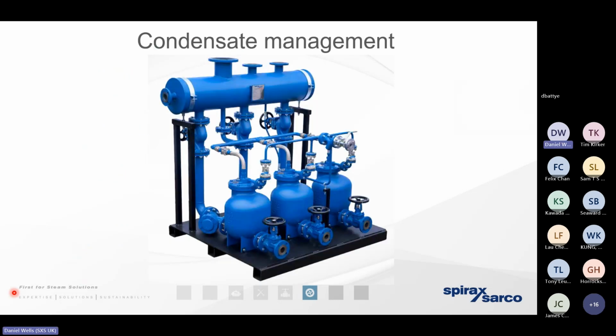Condensate management, as far as I'm concerned, is actually one of the most important and overlooked aspects of a steam loop. Yes, we mentioned heat exchange. That's the reason why so many of our steam using clients are going to have steam on their facility in the first place. We mentioned that steam trapping, in my opinion, is one of the most important components, because if we're not trapping the steam correctly and allowing the condensate to drain away at the appropriate rate, that could be a barrier to heat exchange.